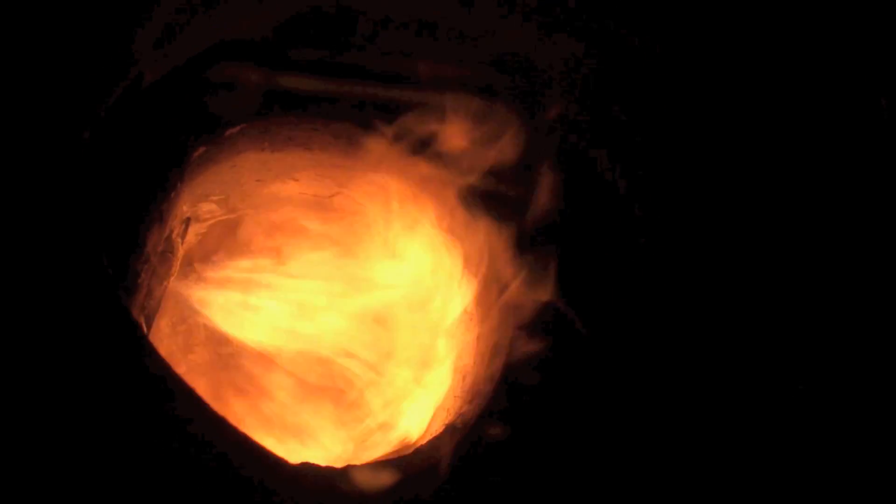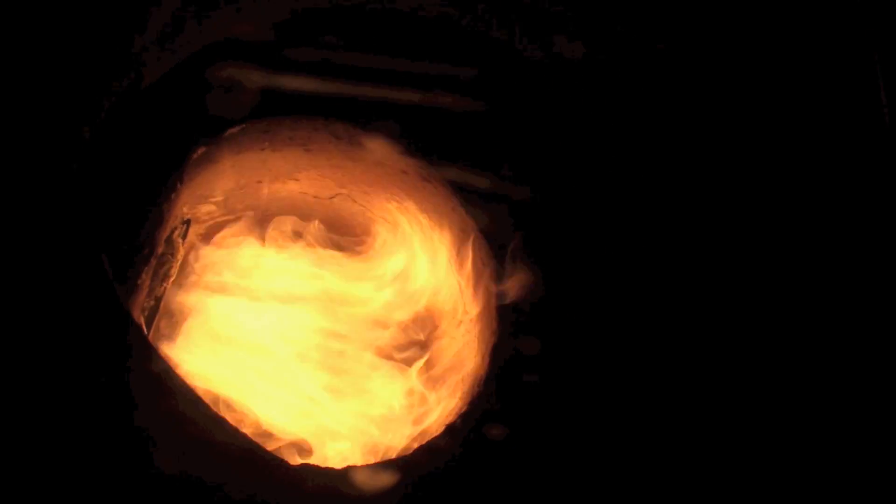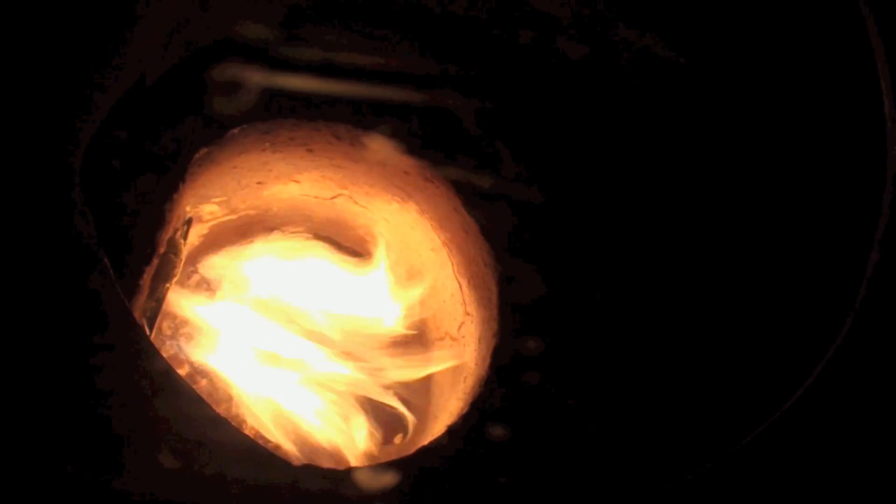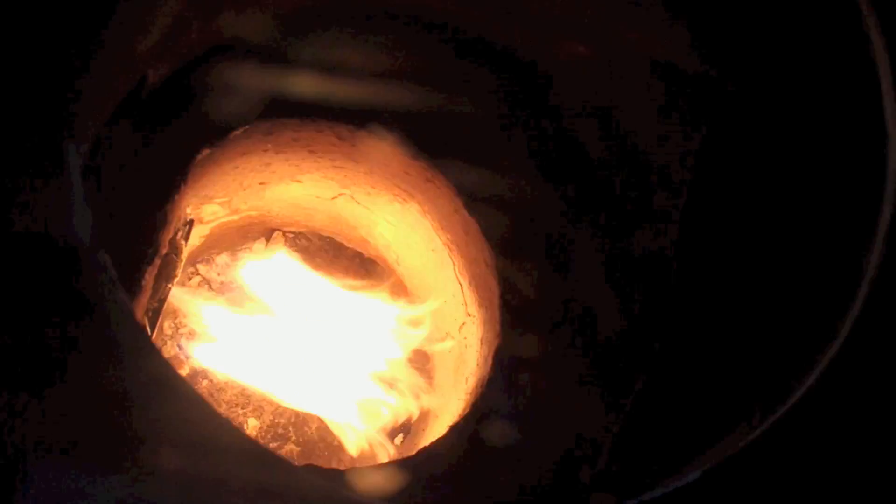And the flame is much larger. Now I've turned it back down again and I'm gonna cut it back to where there's way too much air in. This is a really bad flame.